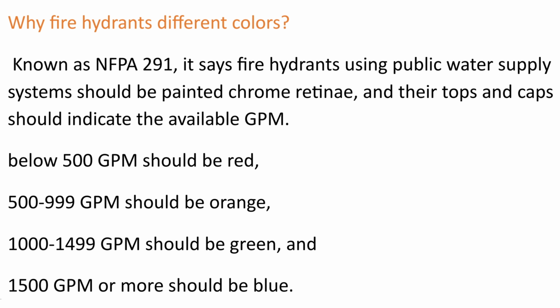Why are fire hydrants different colors? Known as NFPA 291, it says fire hydrants on public water supply systems should be painted chrome yellow, and their tops and caps should indicate the available GPM. Below 500 GPM should be red, 500 to 999 GPM should be orange, 1000 to 1499 GPM should be green, and 1500 GPM or more should be blue.